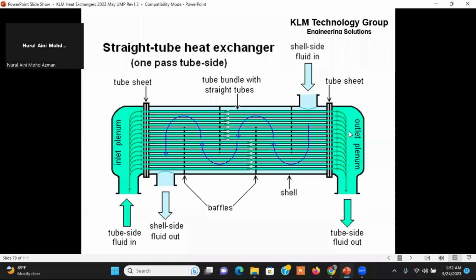So anyway, here's one that's a fixed tube sheet. The problem with fixed tube sheets like this is I can't pull this out to clean these. So these need to be real clean service. Now I can acidize these in place, but I can't water wash them. I can't do much with them in place. So unless it's real clean service, like for a vacuum system, I might do something like this. That's got a really clean surface. Okay.